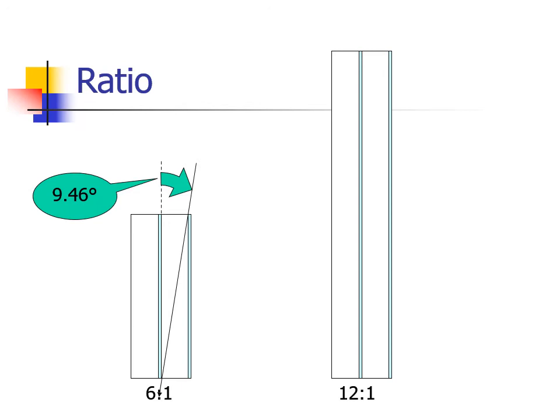Any ray traveling at an angle more than 9.46 degrees from vertical will be stopped by the lead strips of the grid. Or, if the grid is misaligned by more than 9.46 degrees from perpendicular to the central ray, it will stop or cut off the primary radiation necessitating a repeat view.